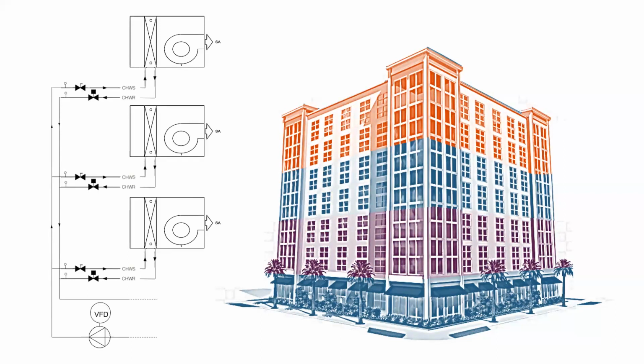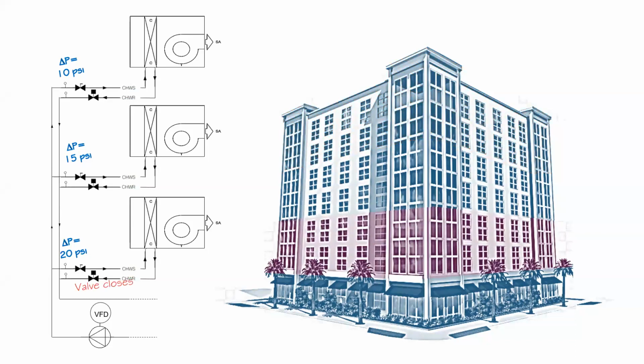It's been split into 3 thermal zones. Each zone is served by a small air handler, as you see here. Since we have a direct return piping system, we know that the pressure drop on each floor will be different. Suppose that the firm on the first floor only works till noon, and with no more load in the space, the valve would close. That means that the flow and pressure drop in that branch goes to 0.